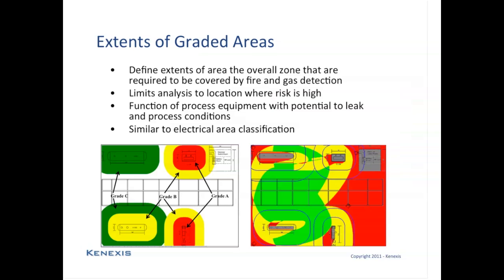Now, how geographic coverage is going to provide adequate results in comparison to scenario coverage is to ensure that the graded areas only extend as far as the hazards occur. When performing a grading, not only are you going to set a category A, B, or C for what are the performance targets, you also want to define the extent of that graded area so that they only encompass the area surrounding the leak sources.